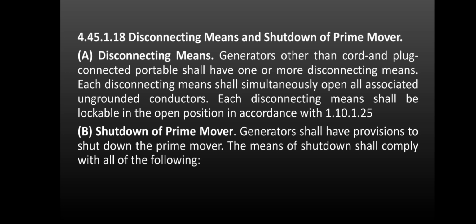Disconnecting means and shutdown of prime mover. A. Disconnecting means. Generators other than cord and plug connected portable generators shall have one or more disconnecting means. Each disconnecting means shall simultaneously open all associated ungrounded conductors. Each disconnecting means shall be lockable in the open position in accordance with 1.10.1.25. B. Shutdown of prime mover. Generators shall have provision to shut down the prime mover.